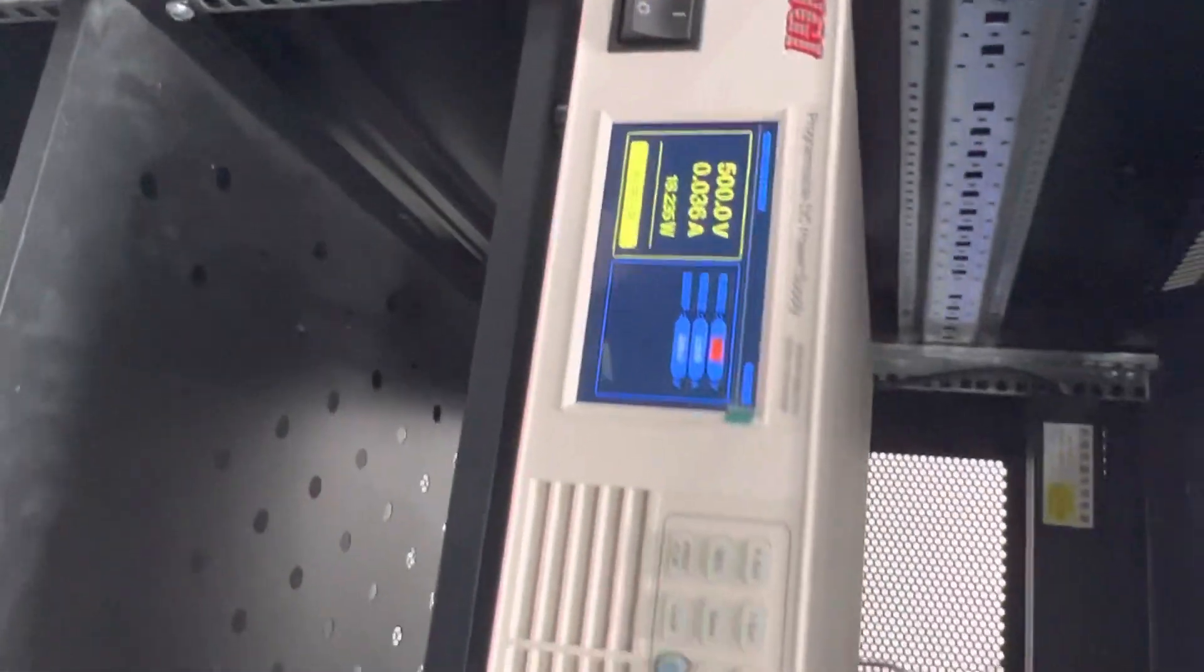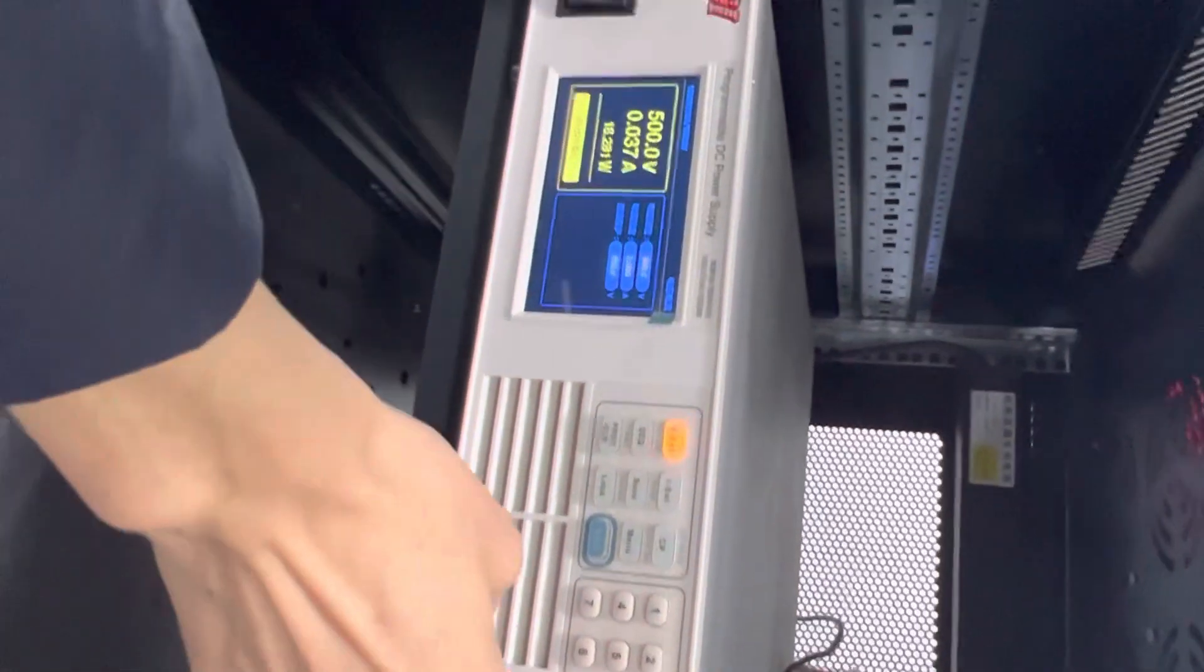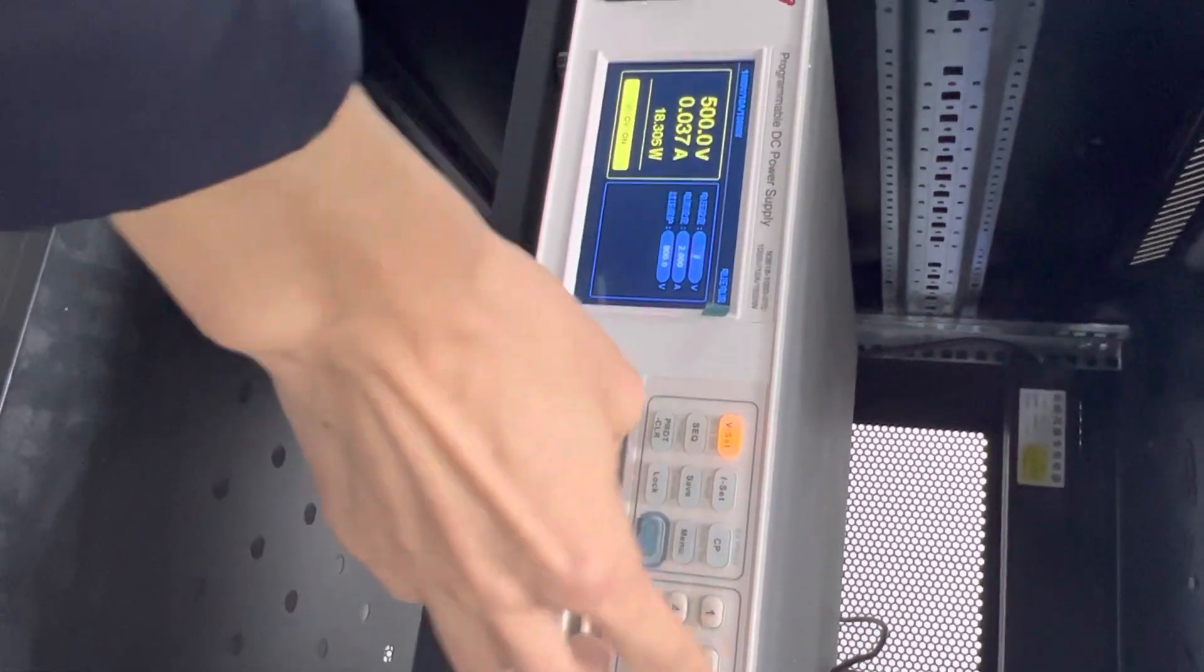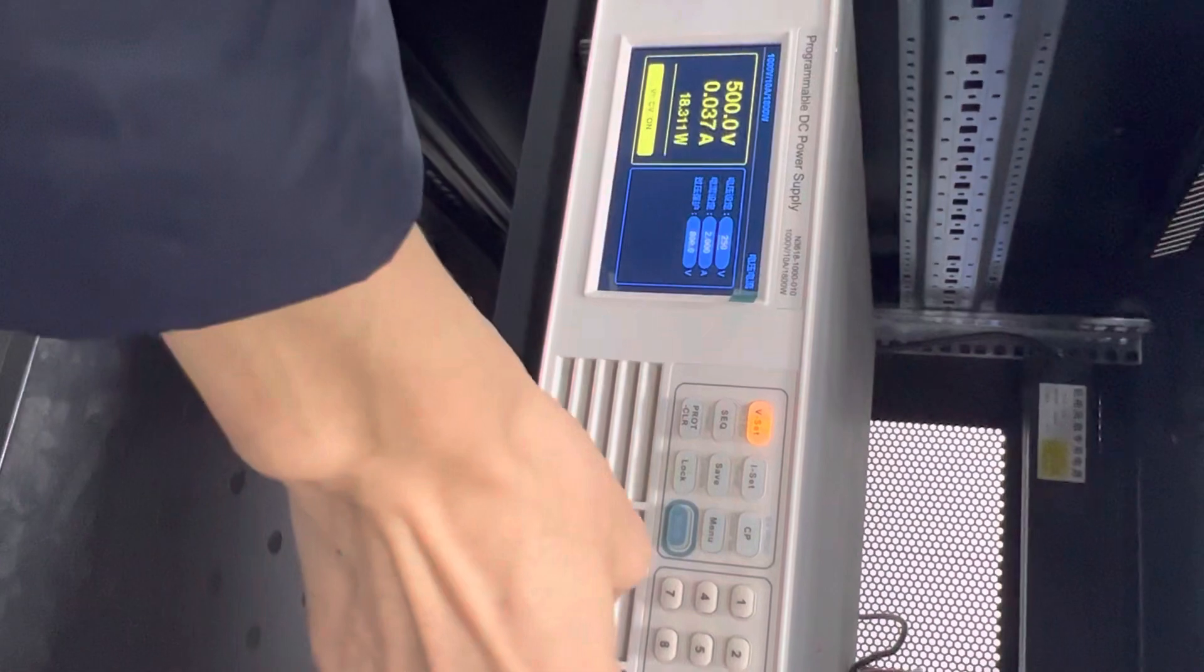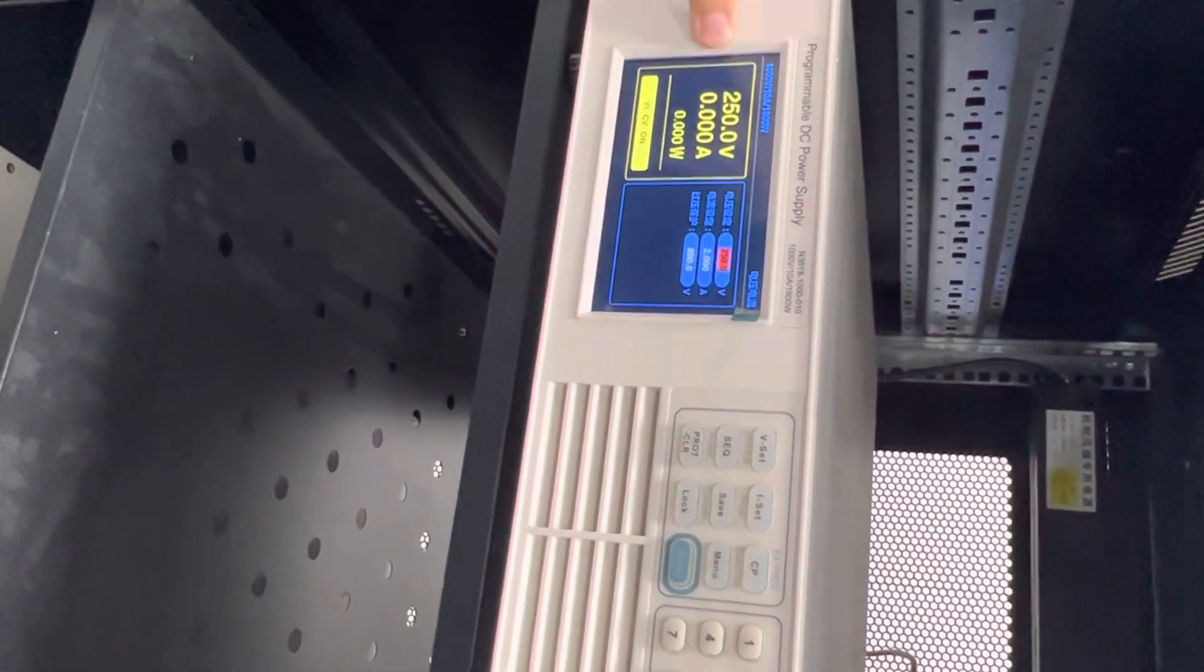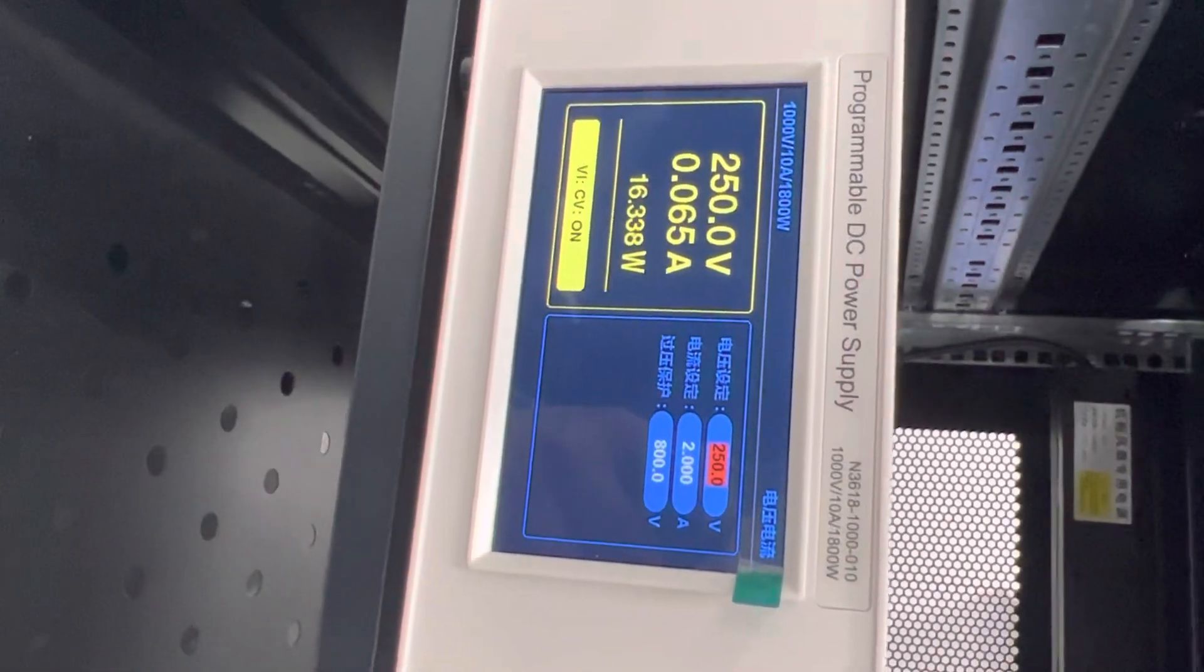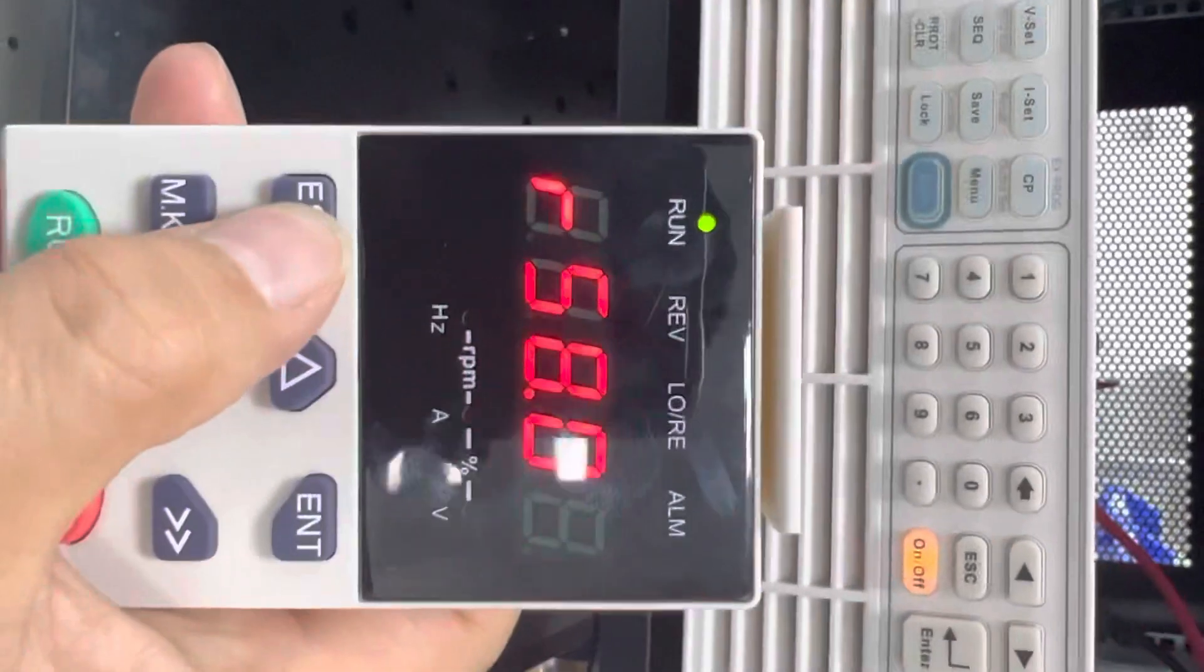Now we can lower the voltage to make the VFD in very low voltage. In normal status without fire mode, it would trip. You can see now it's 250 volts DC, low voltage, but the VFD is still running.